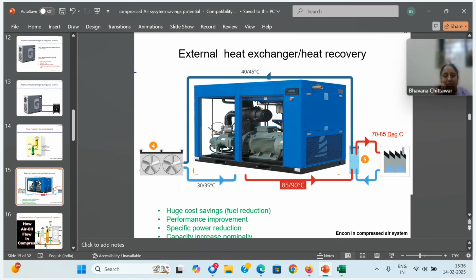So you check for the performance test at the various air temperatures. You record. You will see at the highest temperature, your capacity will go down because of the viscosity reduction in the liquid, our lubricant, so the sealing between the rotors will come down. So air passing will be there, so your capacity will reduce. If you see day and night, always during the night time, your capacity will be more. During daytime, your capacity will be less. This is due to two reasons. One, your ambient conditions are less, so the density of air is higher, you'll get more mass of air being sucked inside, you'll deliver more. Second, air oil temperature is less at night, so your leakage back is less. So that also helps.